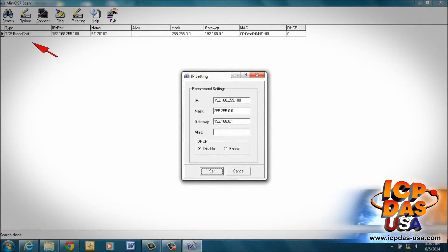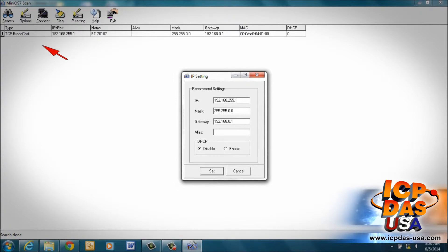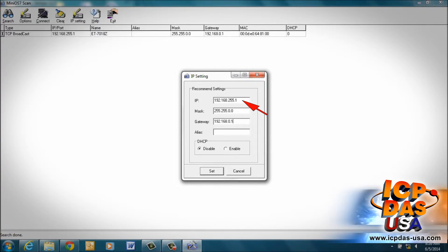After everything is connected, we can use a standard web browser to connect to the module's web server through the IP address. For this application, we will use the ET-7018Z's default IP address, which is 192.168.255.1, but you can change your IP address to work with your network by clicking IP settings.